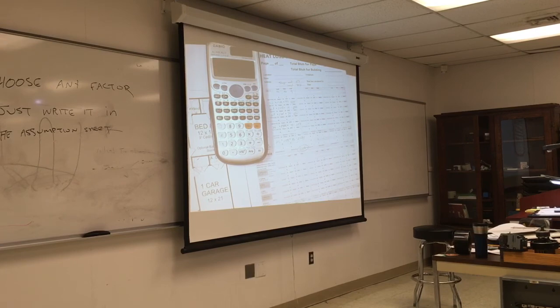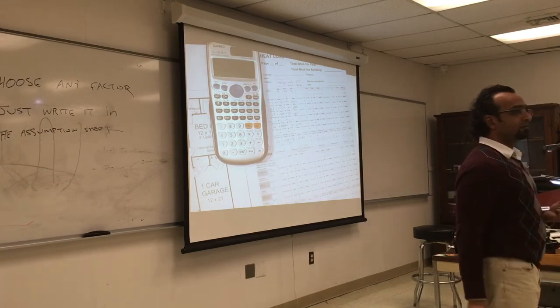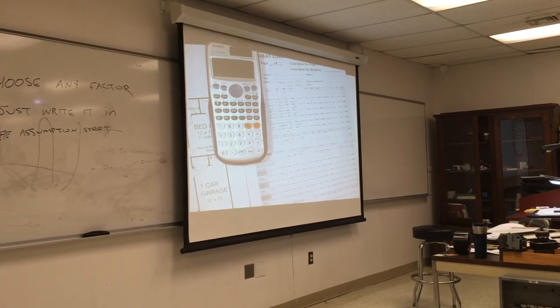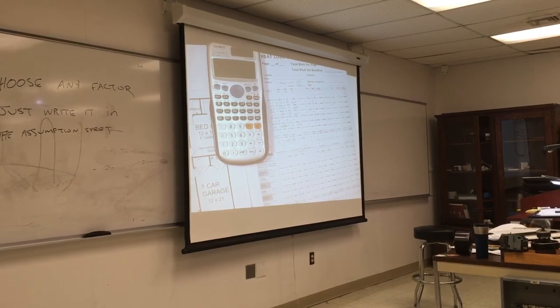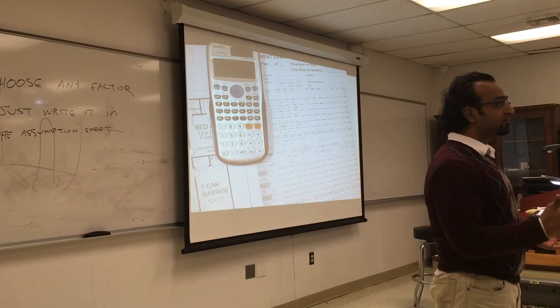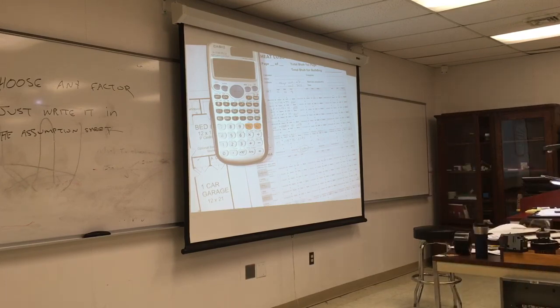The thing is right here. It's a 0.314. Questions? Yeah, 613.8. Nope. Only the wall to the outside. So we put that number. For the walls, you only do walls to the outside, because the outside is where you lose heat. To the inside, there is no heat difference, right? You're heating all the rooms. So walls to the inside do not count.